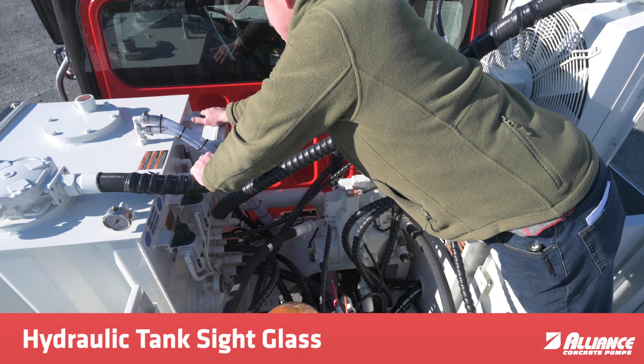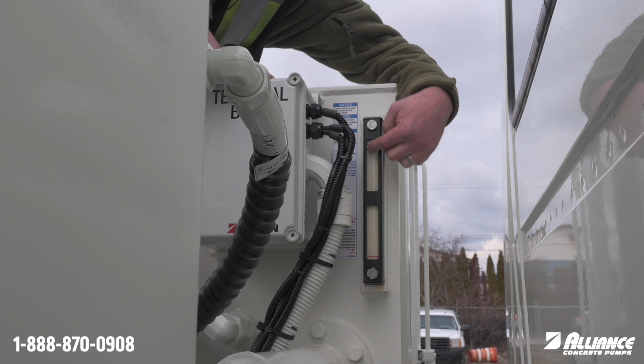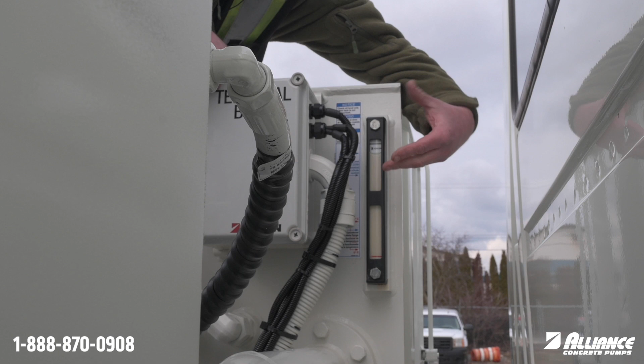So way in front of this terminal box, one thing I didn't see from the other side, but your sight glass is here. This shows a different view of the sight gauge. When you are starting it up, you want to see oil on the gauge and on the top half of the gauge for normal operation. The full line is going to be the black line here on the top of the gauge. You don't want to go any higher than that just because of expansion, but we don't want to go any lower than about right here as well because of the potential cavitation.